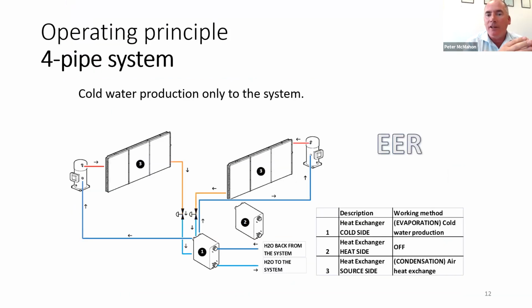So how do they work? Well, you've basically three modes of operation. So we'll go through each mode of operation here slowly because this is really what this is all about. So you can see we've two heat exchangers here, one for cooling, one for heating. And let's just say it's the summertime, you only have a requirement for cooling. So let's say it's a mushroom farm, peak cooling load, no heating load perhaps. Your compressor is pumping a refrigerant through your condenser, on down through the liquid line expansion valve into the evaporator, and then you have refrigerant going back to your compressor. We'll always have two refrigeration circuits, and in this situation, both circuits are dedicated to cooling only.